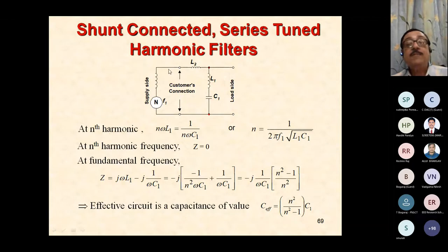So the load side harmonic current has two alternative paths to flow. Path number one, flowing back into the supply, crossing the supply's own source reactance, which will now be n times larger because of the nth harmonic, or it will try to flow through an ideal zero impedance path. In real life, we know it will not be zero, it will be residual resistance, but let's say it will be very low impedance. Obviously, most of the harmonics will flow through this and not flow backwards. So if they are not flowing back, then the line becomes free of that harmonic. All the harmonics will be circulating within this itself.